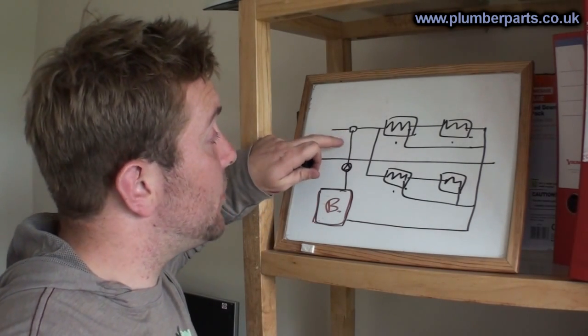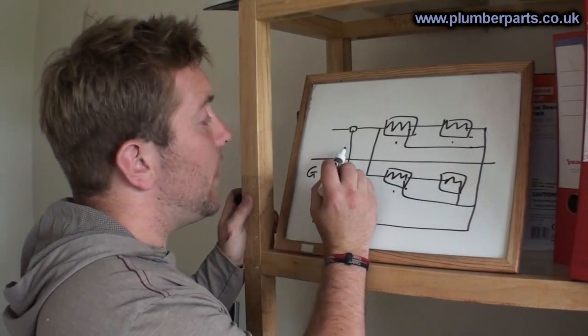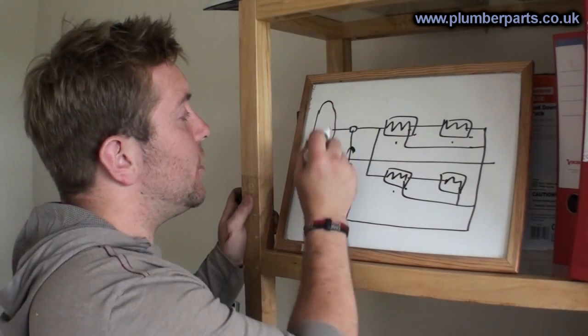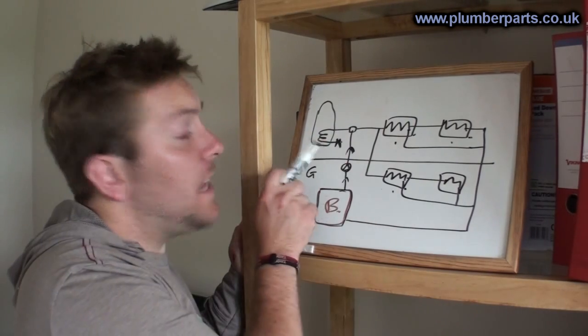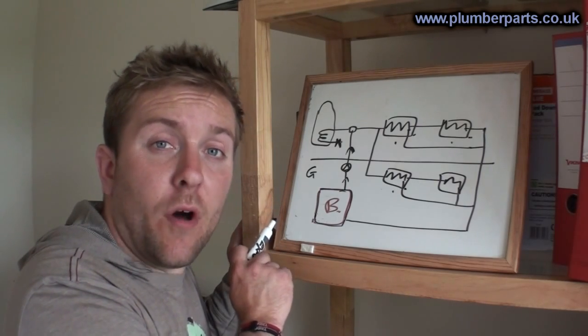You have all your radiators with their flows and returns. We have the flow coming up here from the boiler. It goes through the valve, into our hot water coil in our cylinder, and then back out. And it is here that we fit the flow regulating valve on the return side of the hot water coil. That will go back into the return side of the boiler.